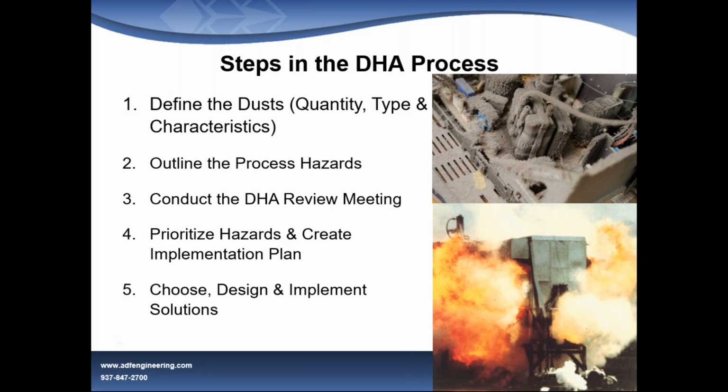But even within those, there are differences in the moisture content. For example, in corn, you may have a difference in the starch content of freshly dried gluten versus gluten meal downstream in the process. You'll find they have different dust characteristics. Differences in particle size distribution will change the dust characteristics, and that's key.